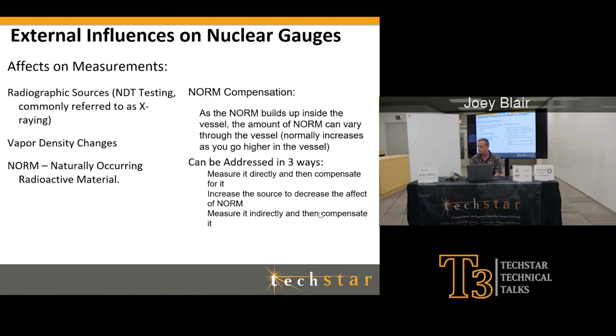Mark is asking: CS-137 primarily decays by beta emission - is it the beta emission we're measuring, or are we measuring beta and gamma emission? We're measuring gamma only. You're right that it decays at beta, but we don't really care about that main decay point, because the detector is shielded in a way that the beta will never make it across that vessel - it'll never penetrate the detector itself. So we've basically canceled out all of the beta decay. The only thing we're measuring is gamma, so that's all we care about.